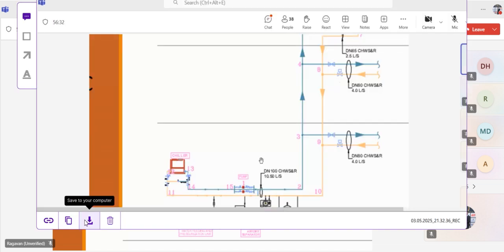And then node number 2, you can see, starts from the riser bottom, and then you have the first floor, the branch line is there. Then after that the pipe size will change, because the pipe size changes based on the flow rate, right? So once the pipe size changes, then you have to change the node number also. Then you can see the second floor. The second floor, the node number I put 4, node number 4. Can you zoom out? Can you zoom out?